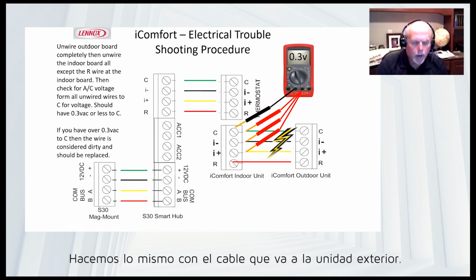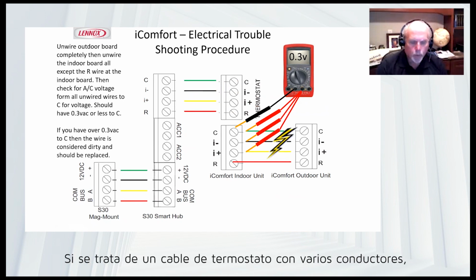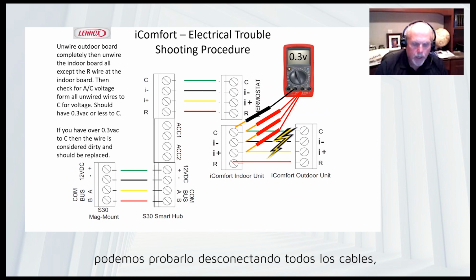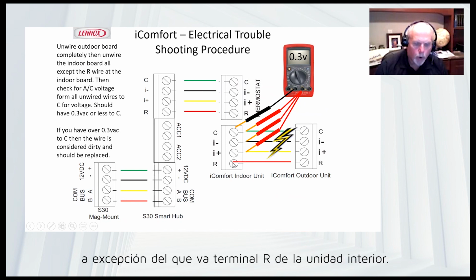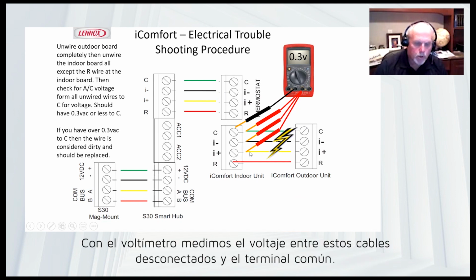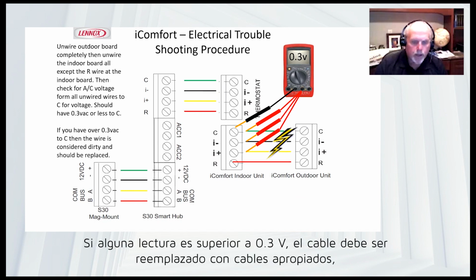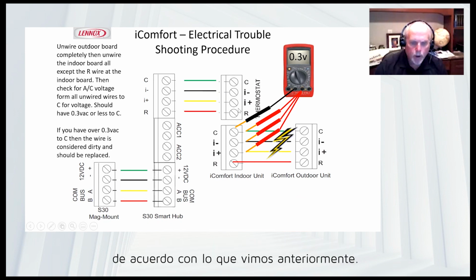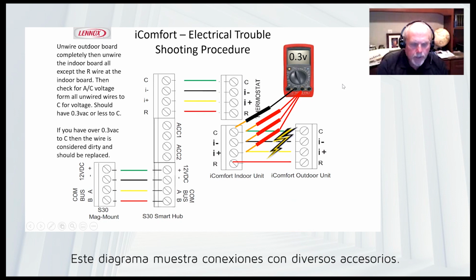And we do the same thing for the cable going out to the outdoor unit. Okay, so again, if this is regular multi-conductor thermostat wire, we can check it by disconnecting all wires with the exception of the one going to the indoor board. Okay, we do disconnect it at the outdoor unit, but the only connection is here at the indoor board at R. And then we take our voltmeter and we check for voltage on these disconnected wires to common to see what kind of voltage we may have bleeding over from the R wire. And we are looking for less than 3/10 of a volt. If we have more than that, the wire is considered bad and needs to be replaced. And hopefully we can replace it with two conductor cables.